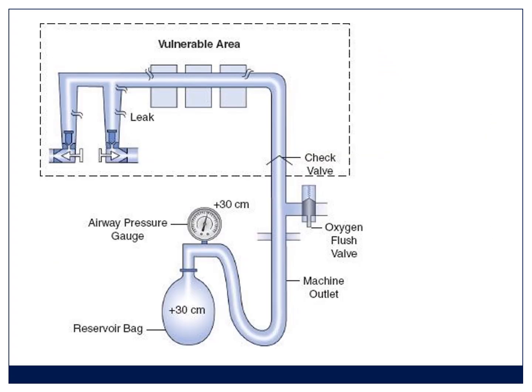So to perform the leak test, you switch the bag or the mode to manual. You check that the APL valve is closed completely, and you press the oxygen flush to get oxygen into the circuit and raise the pressure to about 40 centimeters of water. Some people do this with 30 centimeters of water. And then you compress the reservoir bag, and the APL valve should actually open at 65 centimeters of water. It's designed to open to protect the patient in case the pressure gets high.